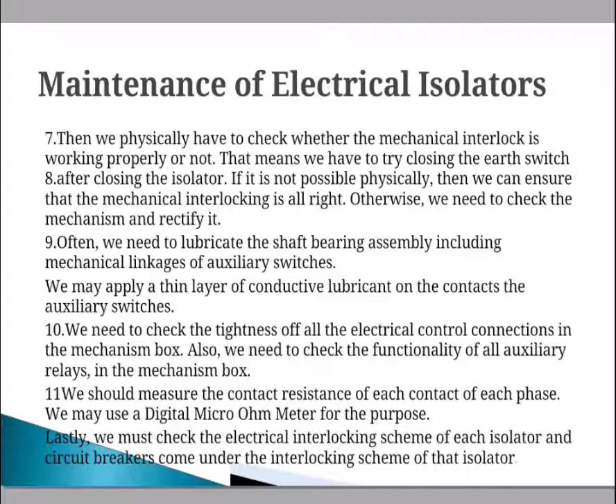For the auxiliary switches, check the tightness of all electrical control connections in the mechanism box. Also check the functionality of all auxiliary relays in the mechanism box. Measure the contact resistance of each contact of each phase using a digital micro ohmmeter. Finally, check the electrical interlocking scheme of each isolator and circuit breaker that falls under the interlocking scheme.